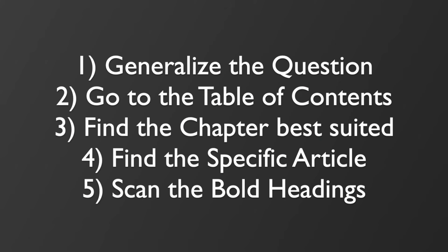The whole of Chapter 300 is wiring methods. General requirements for wiring methods and material. Article 310 happens to be about conductors because you want to know what the ampacity of the wire is. And when you get there, you're probably going to want to go to Table 310.15, which has all of your wire sizes and then a chart that shows all of your ampacities at the same time.